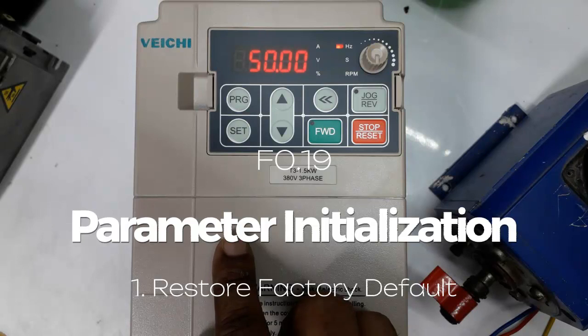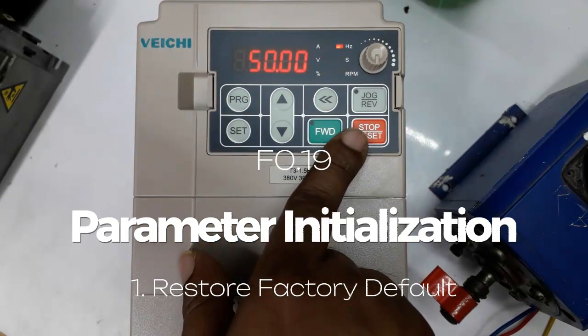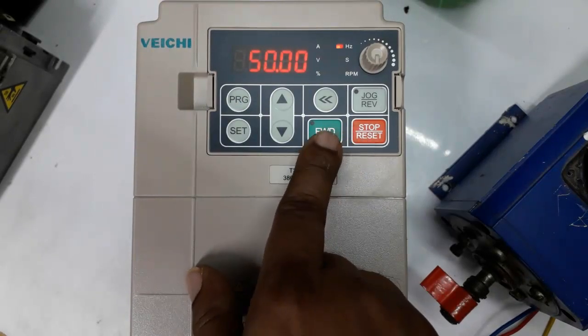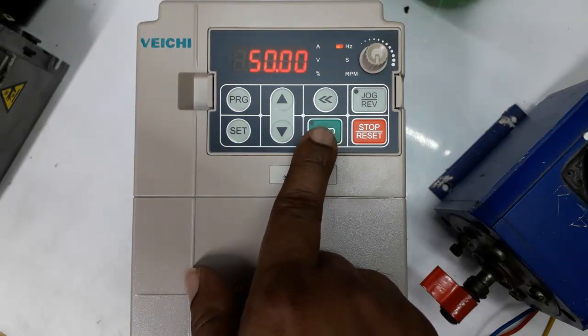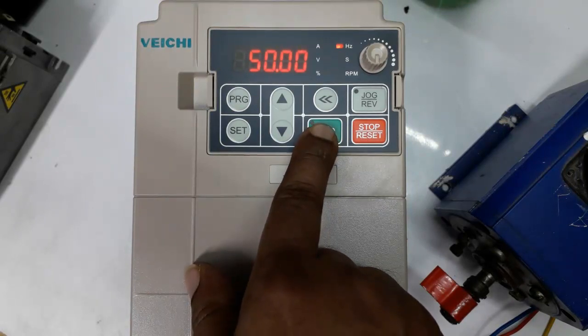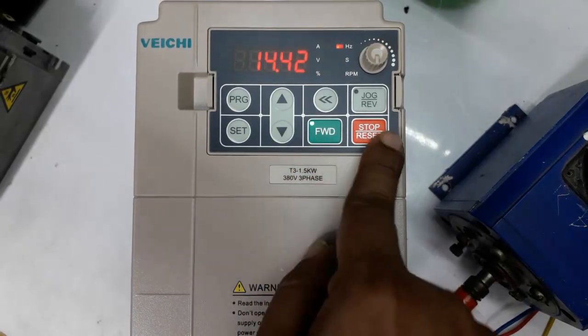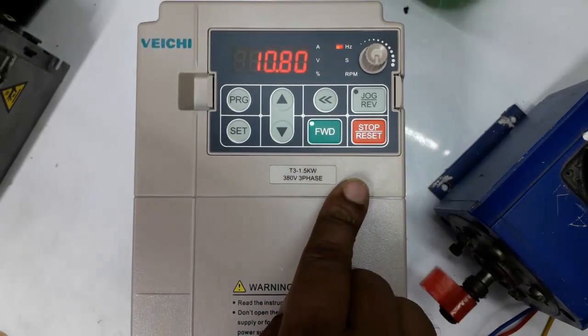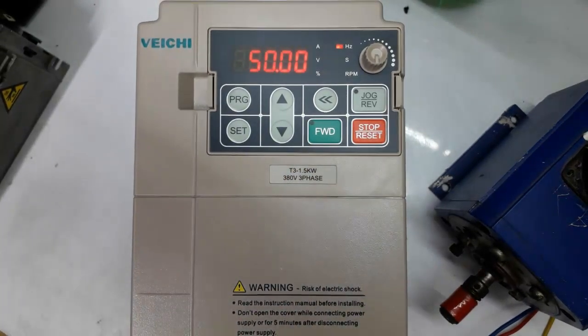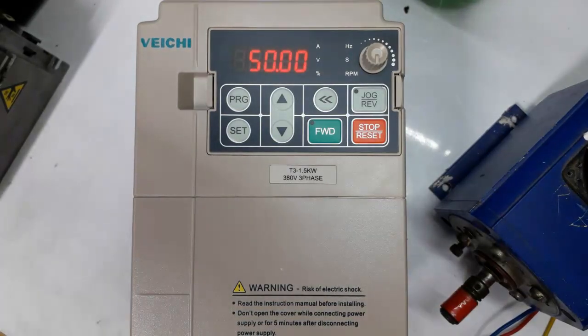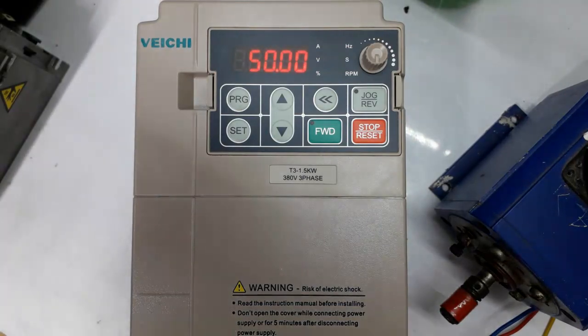Now the inverter is in factory default mode. That means keypad mode is activated. Now only the forward button and keypad mode are activated. We can run this drive by keypad forward button and also stop by keypad stop button. External switch does not work right now because of inverter initialize and its keypad mode is activated.